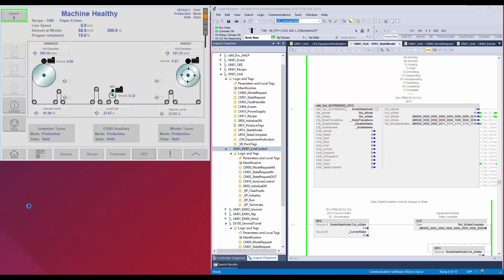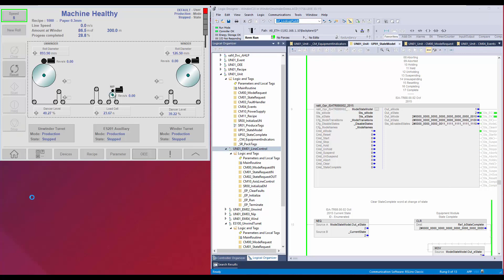To temporarily hold the machine, use the hold command. Now the unit is in held state. In this state, the line master is stopped, but the rest of the axis relations are maintained. When unhold, the line master run is resumed. Now the unit is back to the execute state. To stop the machine and de-energize all the axes, use the stop command. Now the unit is in stop state.